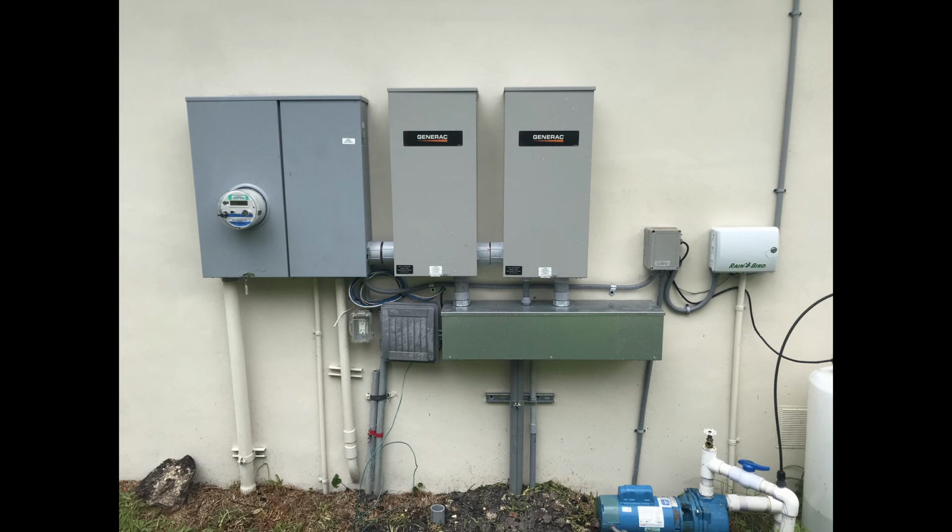You will stay on the generator until the unit again senses that your FPL power is returned, and it will count to 10. And if it sees good power, it will then flip the connection from the generator side to the FPL side. The generator will run for another minute and a half under no load, because now you've taken the load off it. It's not running anything in your home, to cool itself down. And it can do this over and over again.